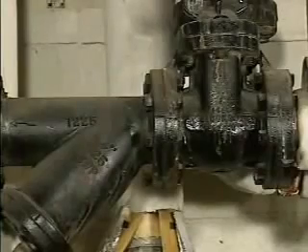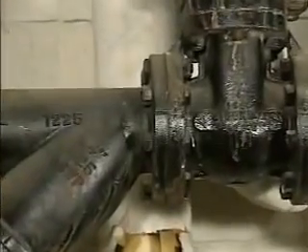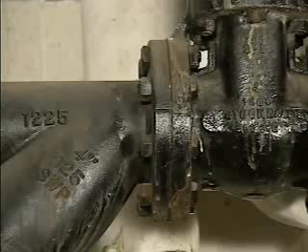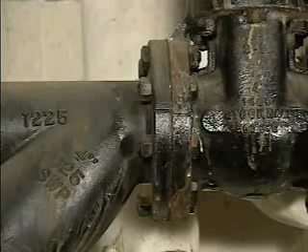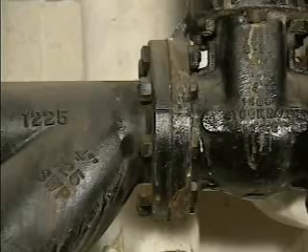and lift heavy loads. Another characteristic of carbon steel is that it's less brittle than other materials, such as stainless steel, so it's able to absorb vibrations. Therefore, it is well suited for systems that generate significant vibrations, such as in vibrators, used to make anodes and aluminum manufacturing processes, lifts, and large gearboxes attached to motors or turbines. Because it is susceptible to corrosion, carbon steel is generally used with non-corrosive gases and liquids.